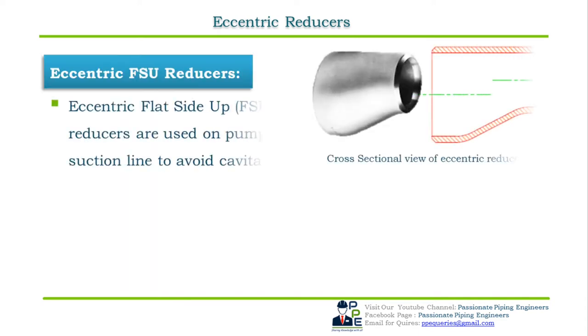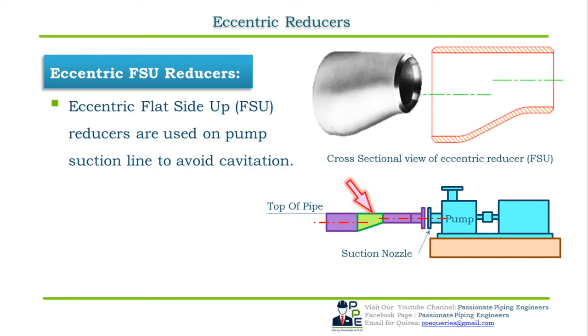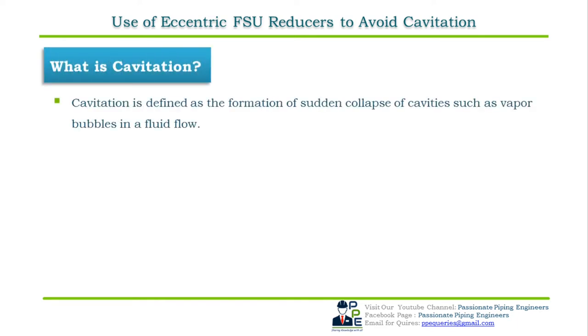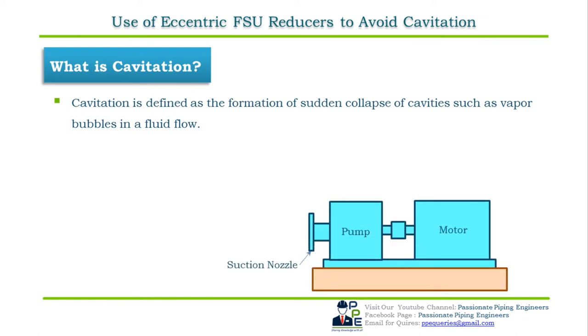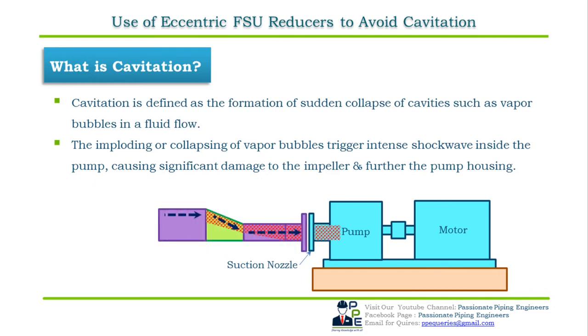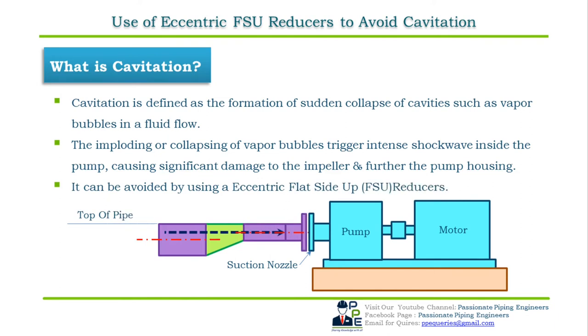Eccentric flat side up (FSU) reducers are used to maintain the upside of the pipe and are used in pump suction lines to avoid cavitation. Cavitation is defined as the formation and sudden collapse of cavities such as vapor bubbles in a fluid flow. A pump is designed to handle liquids, not vapor — the collapsing vapor bubbles trigger intense shock waves inside the pump, causing significant damage to the impeller and pump housing. Using a concentric reducer or flat side down reducer can create this problem; it is avoided by using a flat side up reducer.